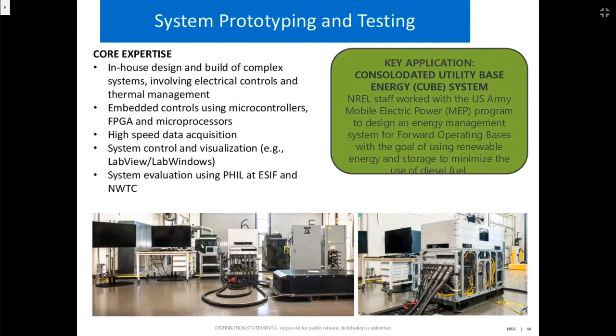So we've got the TQGs you can see in the background here. They're inside and plumbed to a carbon exhaust inside the laboratory. This system was run using the load profile received from Army REF and E2S2 as a viable load profile that covers the bases for a forward operating base. We ran it for a couple of 24-hour tests and recorded in an intricate way the diesel fuel use and consumption. In line with those TQGs, we had a Coriolis flow meter that gave us a highly accurate reading of how much fuel was consumed.